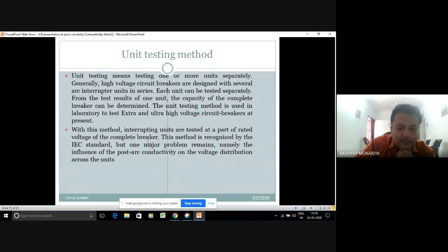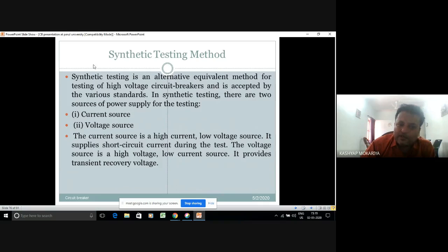With this method, the interruption units are tested at a part of the rated voltage of the complete breaker. This method is recognized by the IEC standard. But one more major problem remains: the influence of the post-arc conductivity on the voltage distribution across the units. We have to be careful while conducting this type of test.